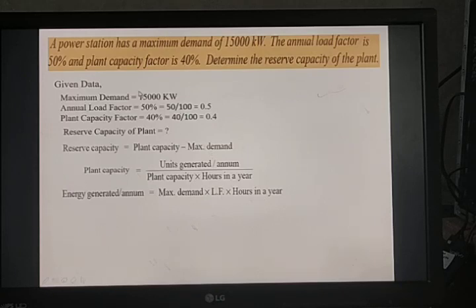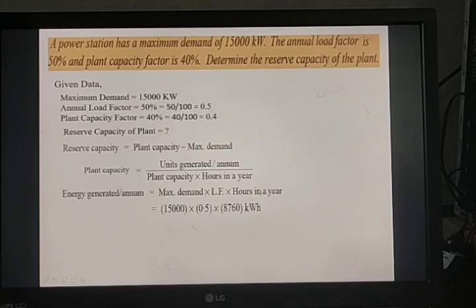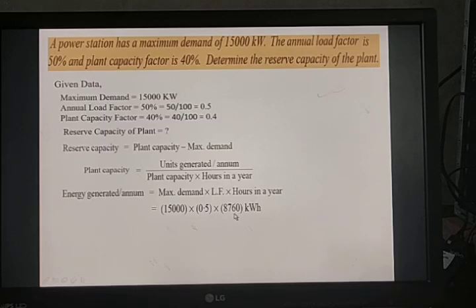Substituting: maximum demand = 15,000, load factor = 0.5, hours in a year = 365 × 24 = 8,760. Units generated per annum = 15,000 × 0.5 × 8,760 = 65.7 × 10⁶ kilowatt hours.